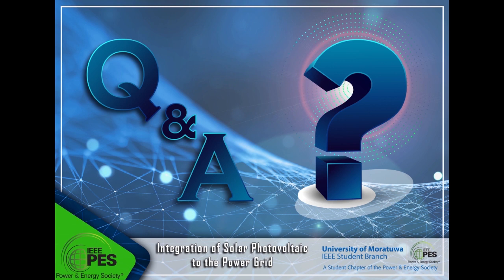And with weak systems, if we are using a PLL to synchronize the converter to the grid, tuning of the PLL is one of the biggest challenges, choosing the proportional and integral gains of the loop, KP and KI. The best values of those are not the same under different operating conditions. So how do you come up with a set of values that are robust to the range of operating conditions?